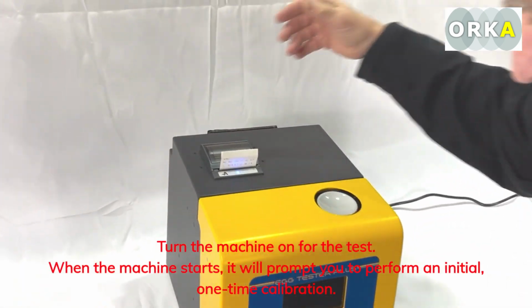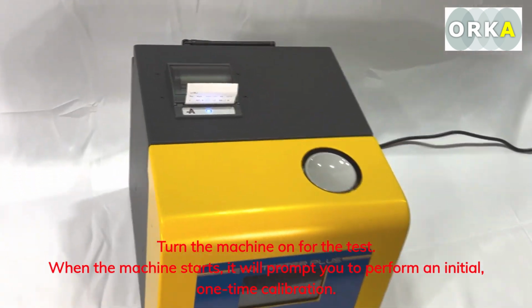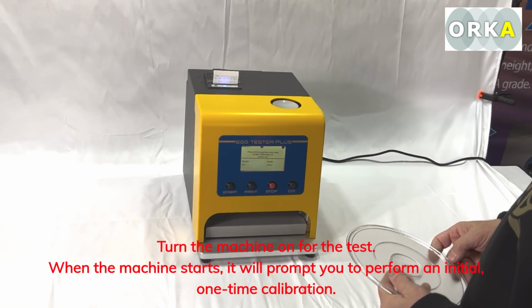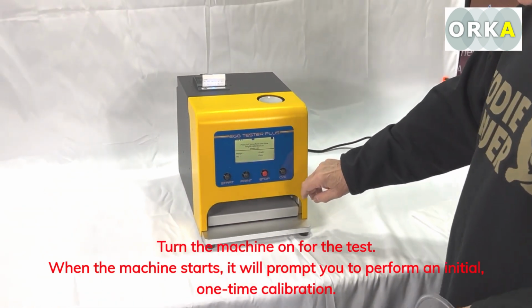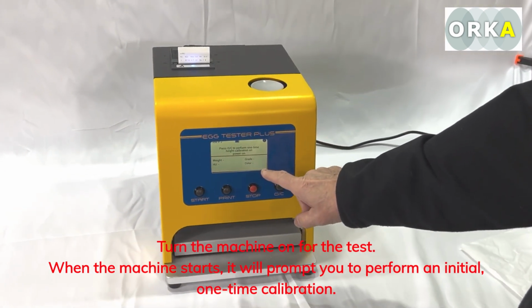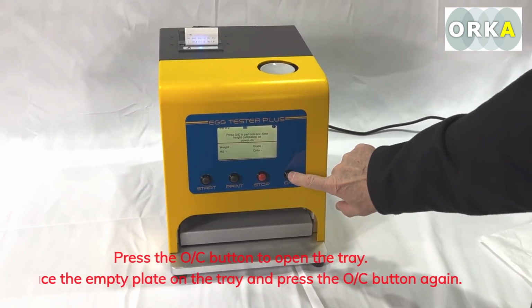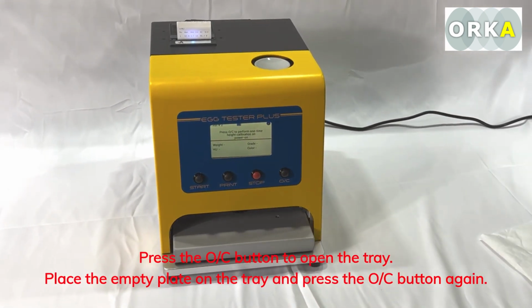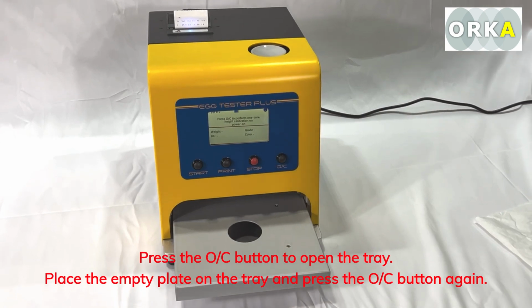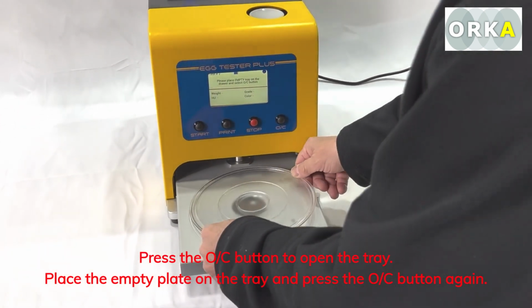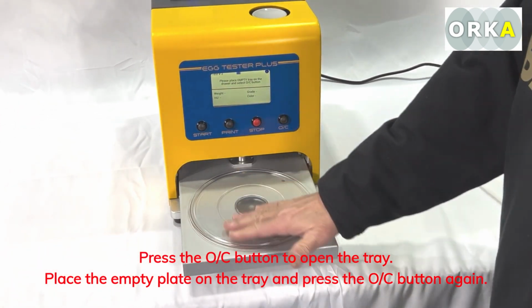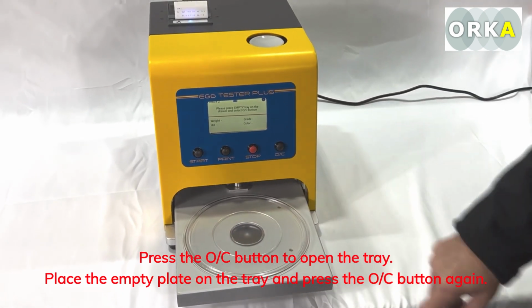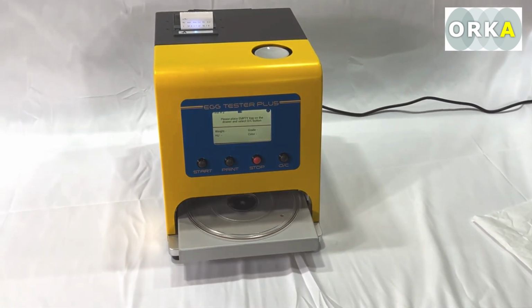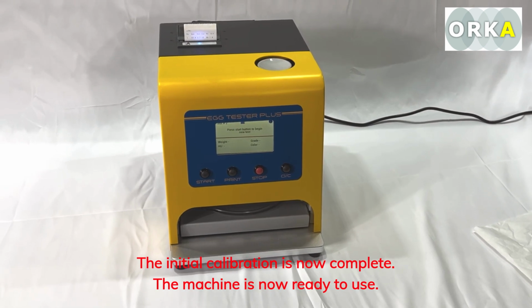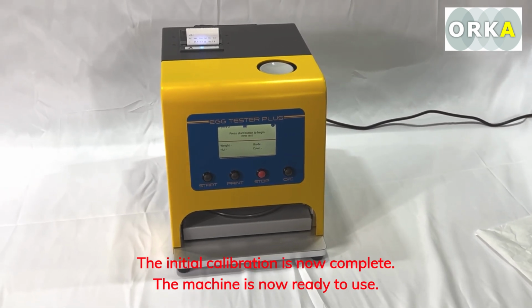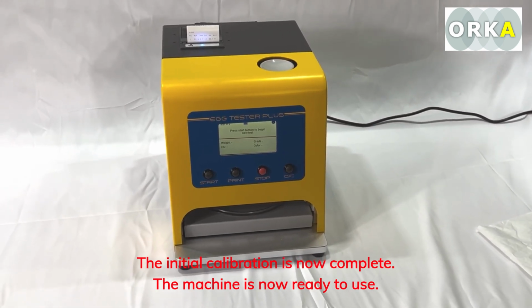Turn the machine on for the test. When the machine starts, it will prompt you to perform an initial, one-time calibration. Press the OC button to open the tray. Place the empty plate on the tray and press the OC button again. The initial calibration is now complete. The machine is now ready to use.